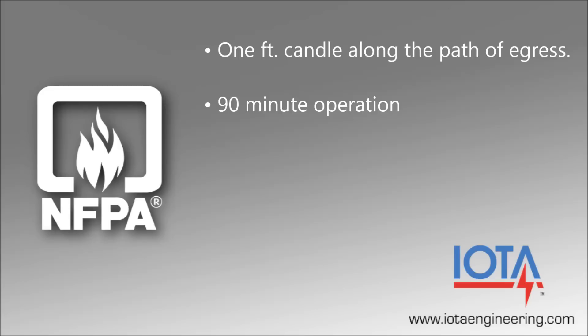In some cases, a longer duration may be required. FEMA guidelines, for example, dictate a two-hour runtime for emergency lighting used in tornado-safe rooms. Additionally, the National Electric Code requires emergency lighting along the building's path of egress to assist occupants to a safe haven.